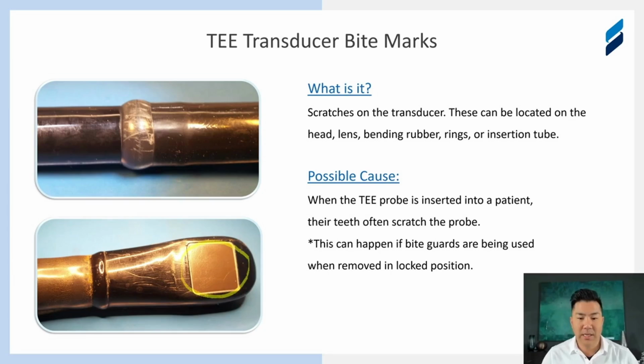I'm circling this in yellow and red to be a little more visually acceptable. If you start scratching against that lens, now you're actually putting impact and pressure on the crystal itself, this most sensitive part of the probe. So to protect the probe, and probably cause a little less discomfort for the patient, release the mechanism that locks the probe into place, and then go ahead and remove it from the patient.